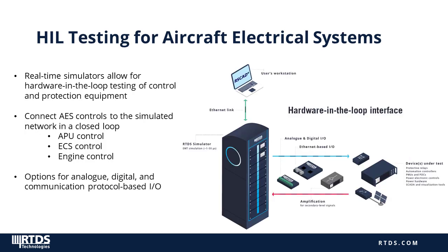With the RTDS simulator, we take that EMT simulation and run it in real-time using dedicated real-time simulation hardware to achieve real-time operation at the time steps mentioned. The principal advantage of real-time operation is that it allows power system protection and control equipment to be connected to the simulated environment in a closed loop for testing. We can send values from the simulated aircraft electrical system to an external auxiliary power unit controller or engine control system, and receive feedback from those devices in real-time for an accurate picture of how equipment and the system respond dynamically. External devices can be connected via analog and digital signals or communication protocols such as Modbus.